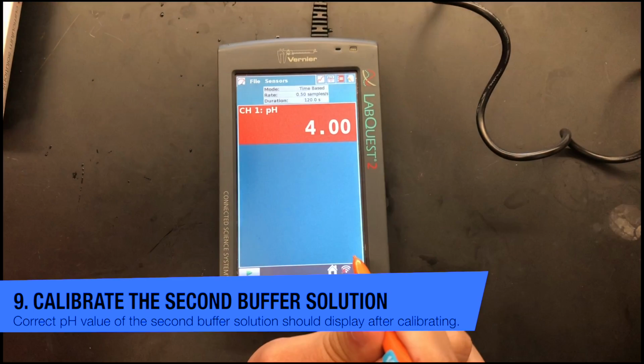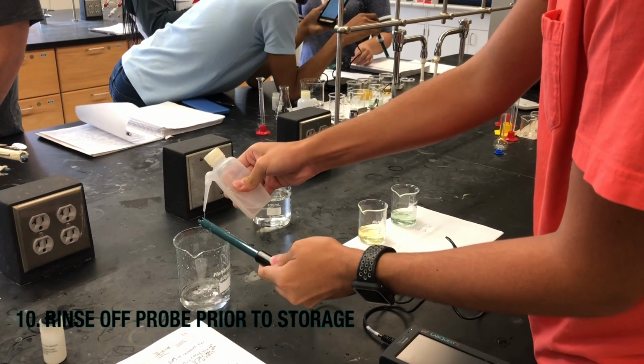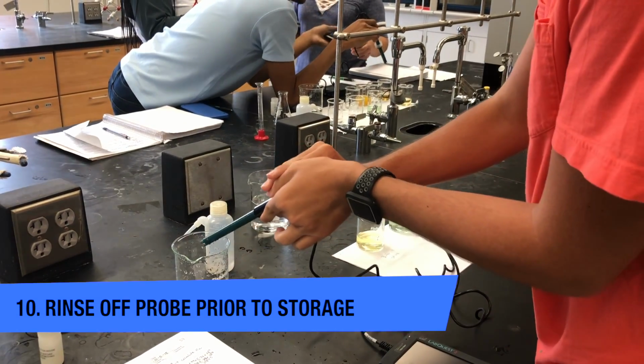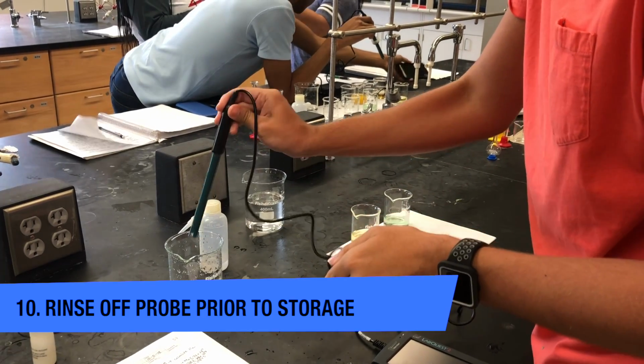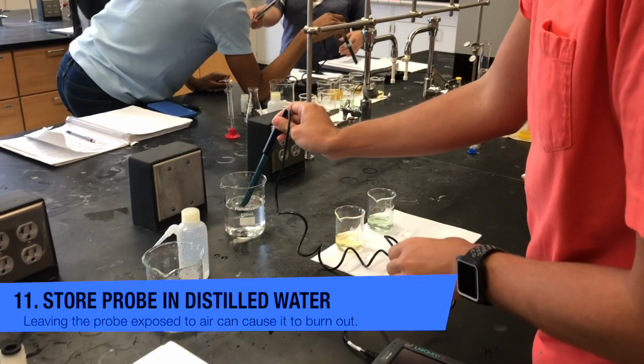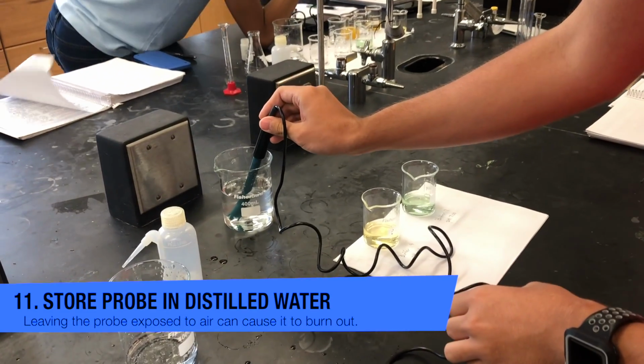Now check to see if the correct pH is displaying. Rinse off the probe and place it in distilled water for future use. Allowing the probe to sit out in the air could cause it to burn out.